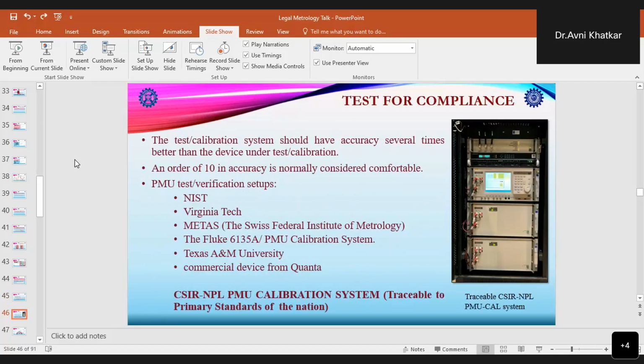Now, for testing and calibrating any type of device, the test or calibration system should have an accuracy several times better than the device under calibration. And an order of 10 in accuracy is normally considered comfortable.